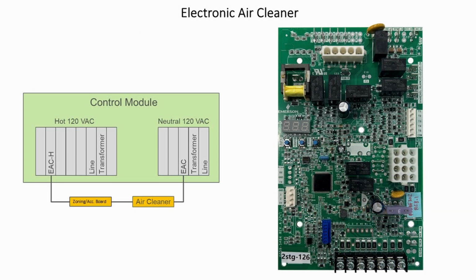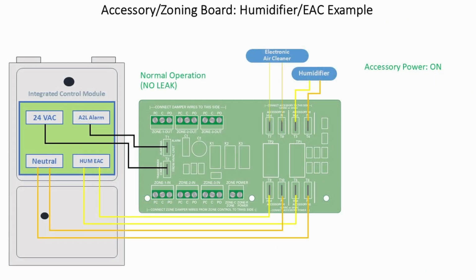Electronic air cleaner. On the control module, there are terminals for 120 volts AC hot and 120 volts AC neutral to provide power for an electronic air cleaner, connecting a zoning and accessory board. Accessory zoning board, humidifier and electronic air cleaner example.